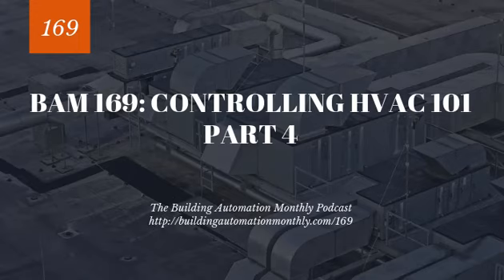So I know, really confusing, but if you've messed around with steam coils and air handlers, that makes complete sense. If not, just make sure you kind of study this, because it's a little funky as far as sequencing. You definitely want a very slow acting PID loop, and you want to get as accurate with your pressure control of those pneumatic actuators as possible.